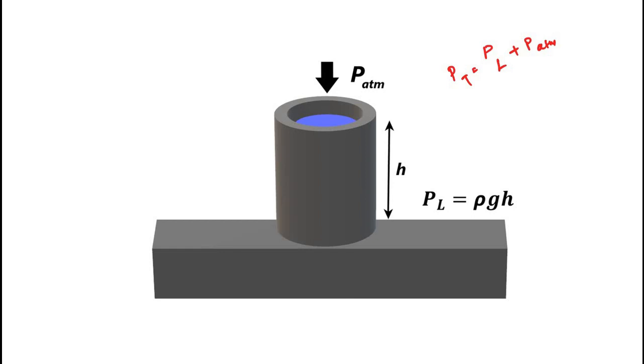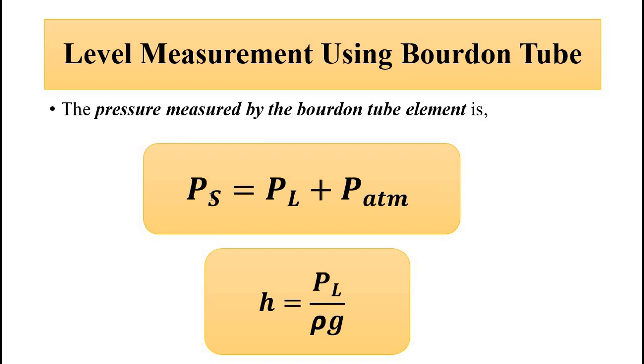The atmospheric pressure is a constant value, so we subtract it from the total pressure, that is the sensor pressure. The pressure measured by the Bourdon tube is the total pressure, which is the liquid column pressure and the atmospheric pressure. So we subtract the atmospheric pressure from the total pressure measured by the sensor, which gives us the liquid column pressure. That is equal to rho g h.